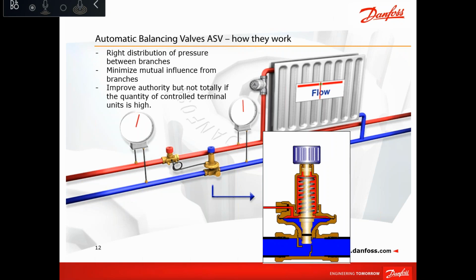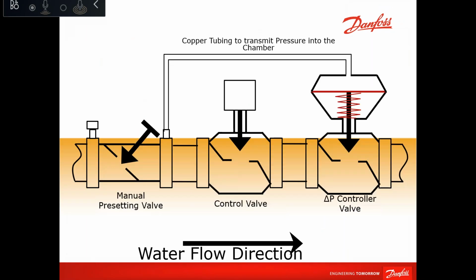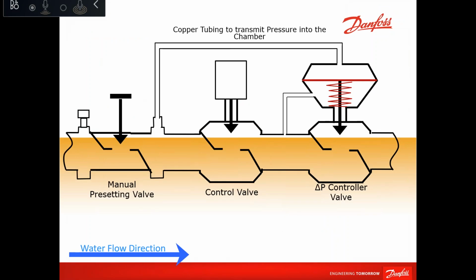So if we combine a two-way valve with a manual balancing valve and a DPCV, we will have a pressure independent balancing and control valve. So a PICV is the combination of all the balancing solutions available as of now, which means DPCV, manual balancing valve, and then a two-way valve.